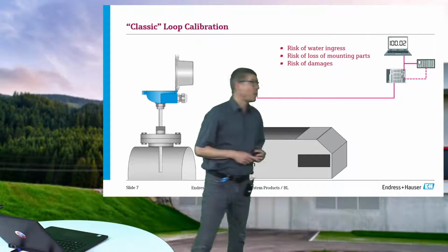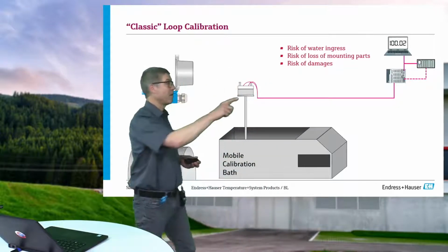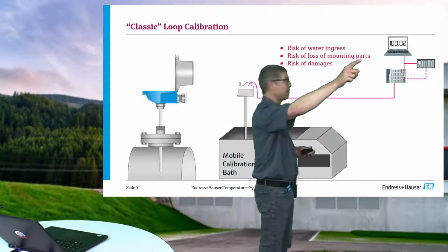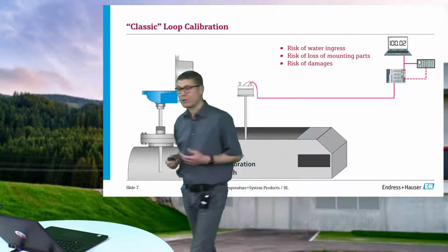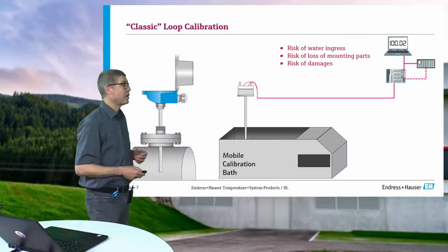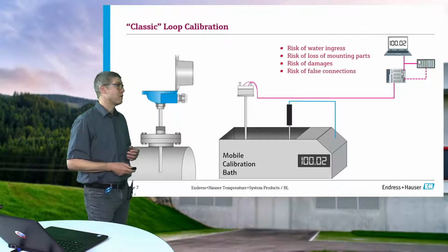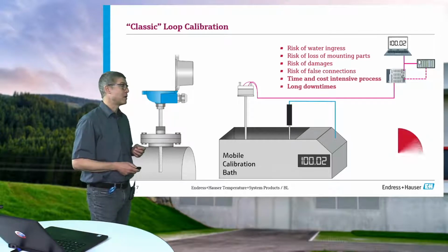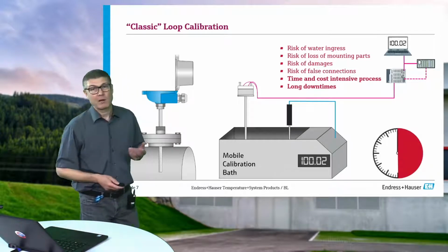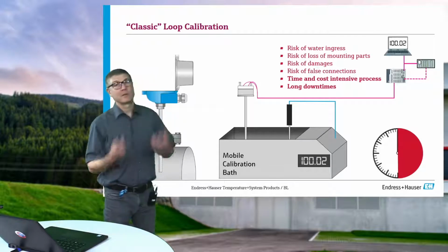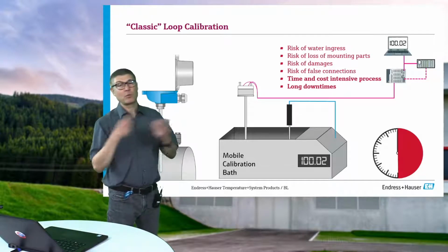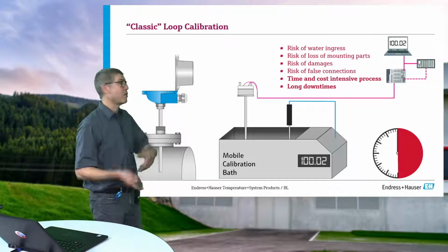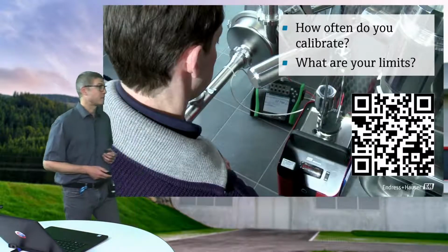In this case, at 100 degrees, you see the indication of the PLC is nearly 100, so it seems everything is fine. And you can imagine, you have your reference thermometer too. That is some work. You have to dismount it, disconnect it, put it to the bath, connect it again, and the other way around. It takes a while.